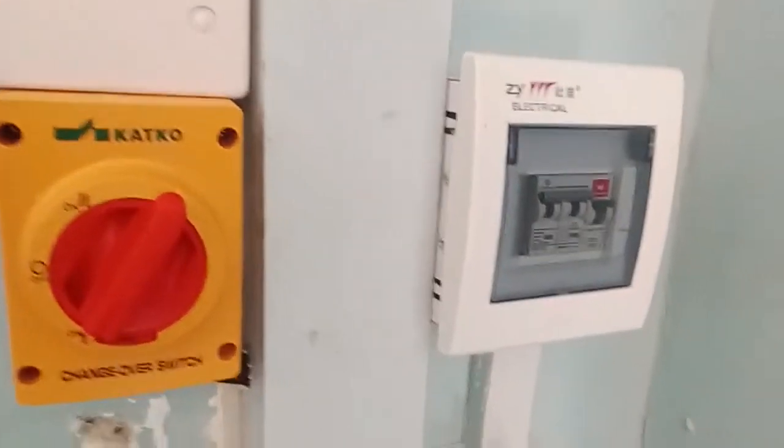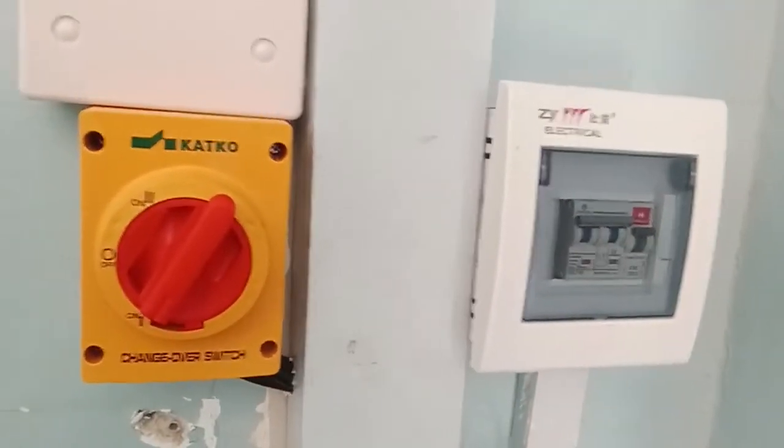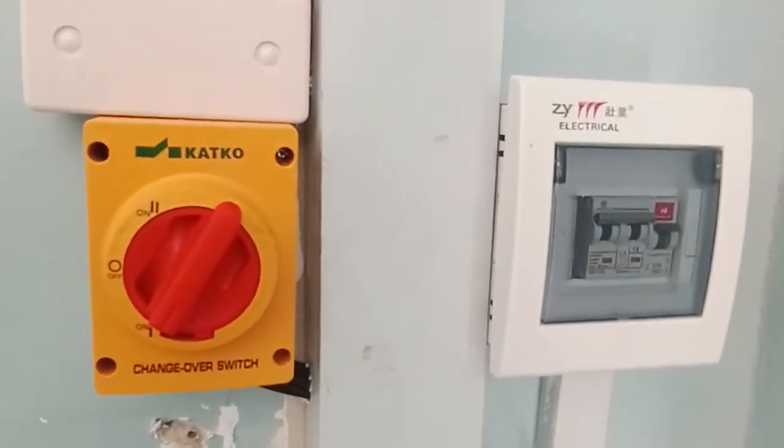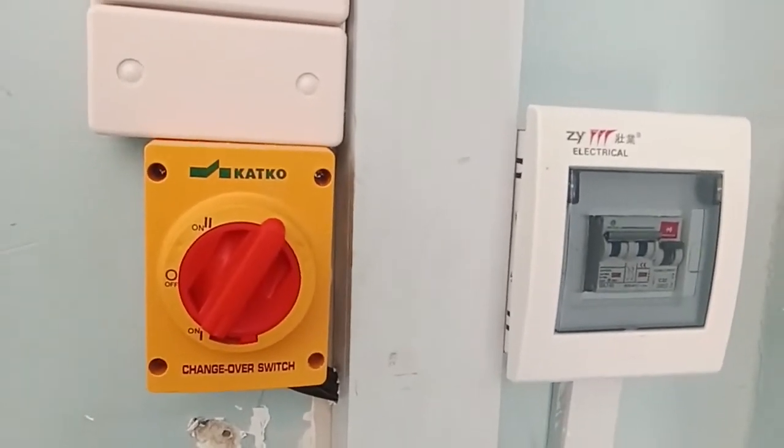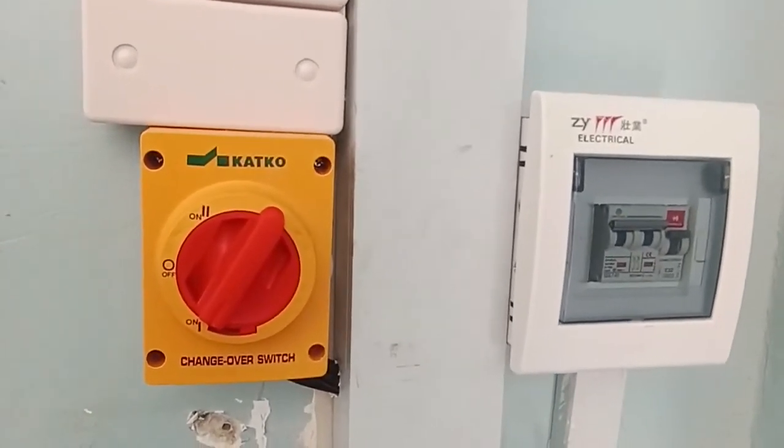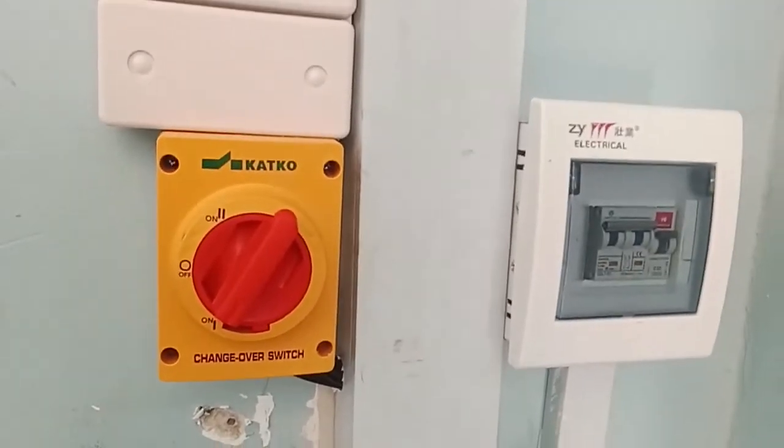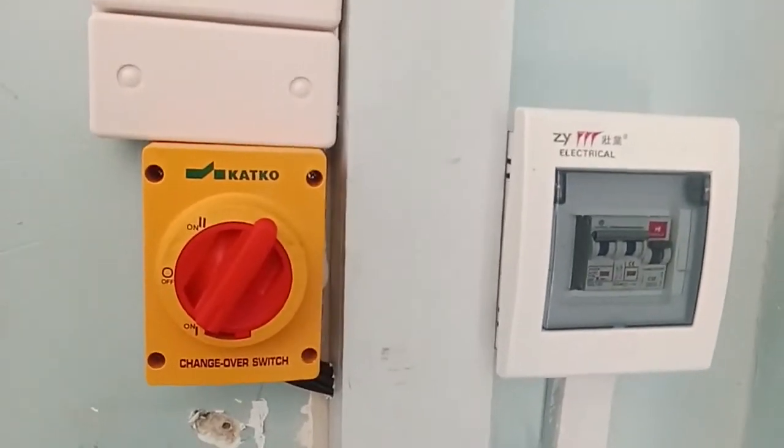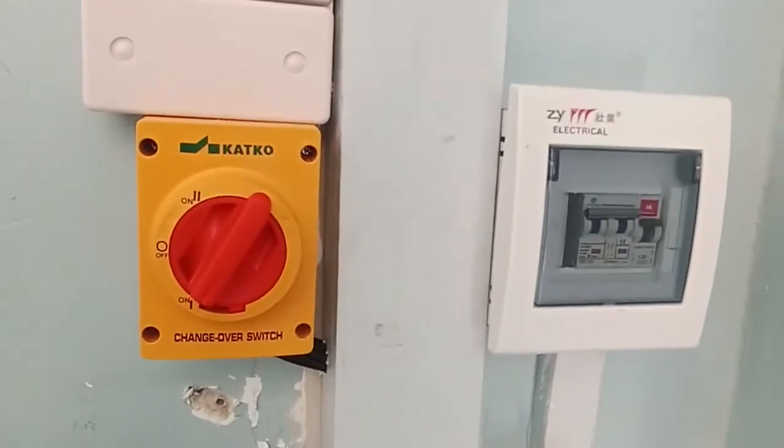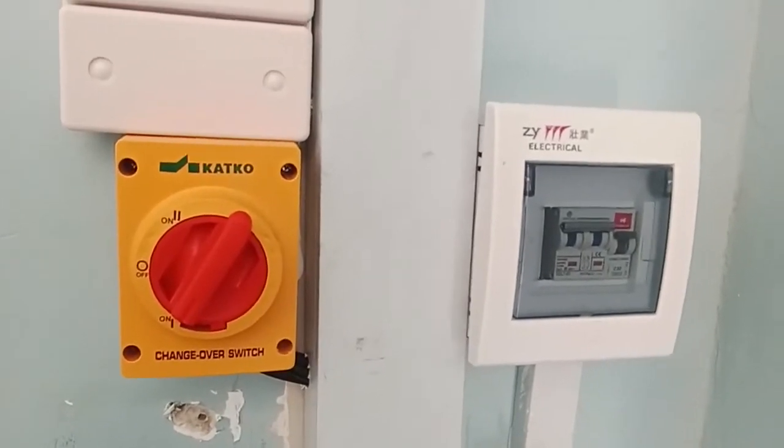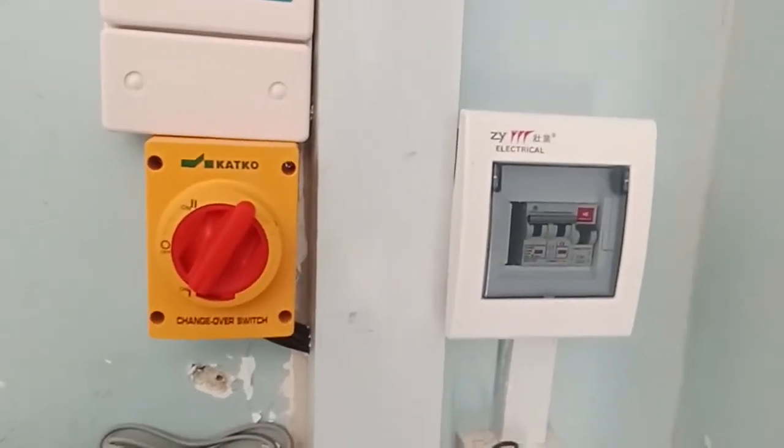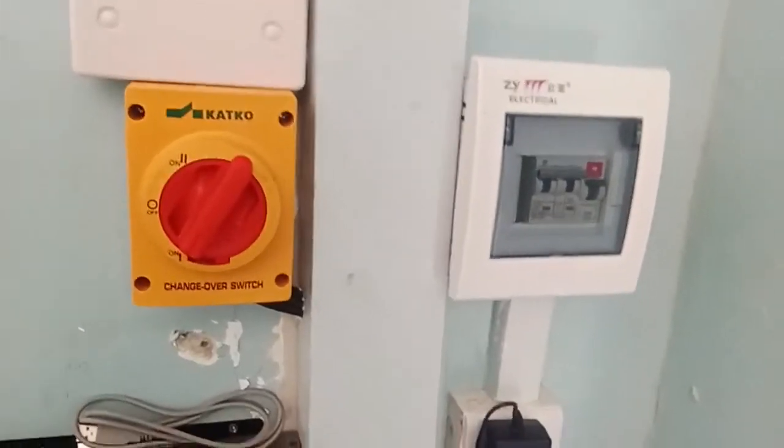Then, as you can see also there, we have a changeover switch. This is a bypass switch, which in case the inverter fails, the client or the clients in charge will be able to bypass the inverter and continue using the mains grid in case it is available, and the inverter fails before they call for any technical assistance.